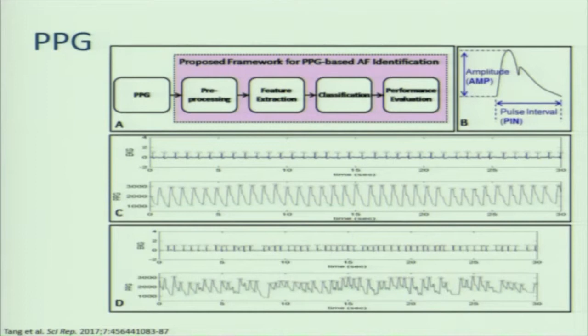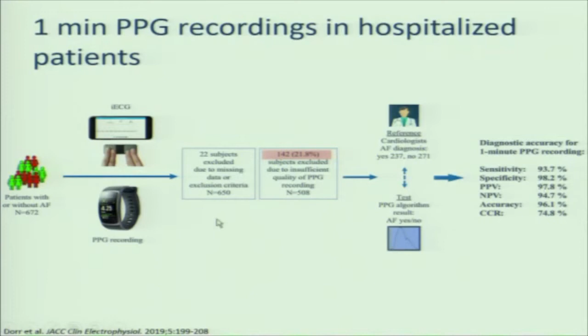If you look at data around PPG, this is one study of about 600 patients who were hospitalized, and they screened them using a watch that was PPG enabled and simultaneously obtained an EKG using a smartphone. Something that's important to note, about 20% of the PPG recordings in this cohort were uninterpretable, either because the contact with the wrist wasn't very good or other reasons for the data not being usable. So with any of these devices, there tends to be a fairly high rate of uninterpretable data, and we'll come back to that. But if you look at the 80% or so of the data segments that were interpretable, sensitivity is about 94% for the detection of atrial fibrillation, specificity of 98.2%. So again, the PPG, if you can interpret the data, seems to work quite well.